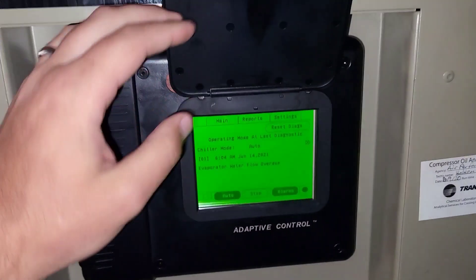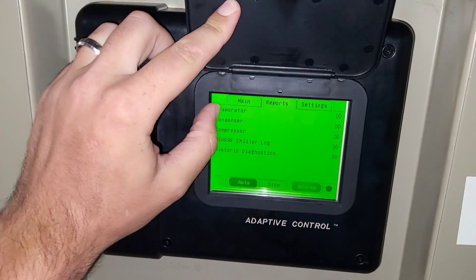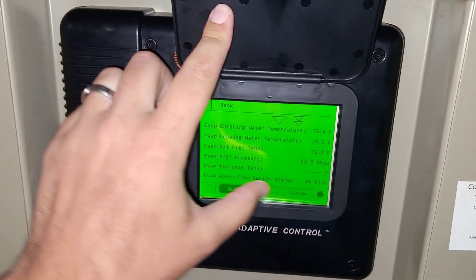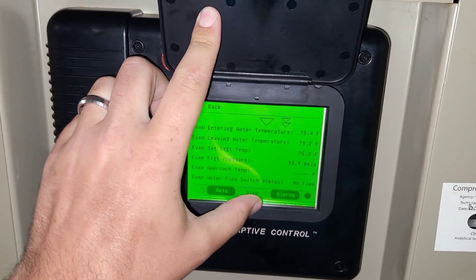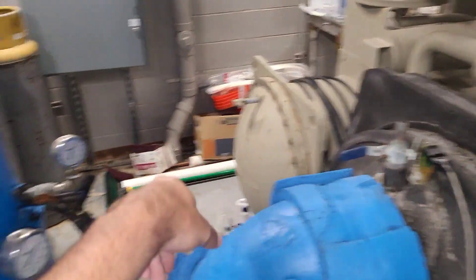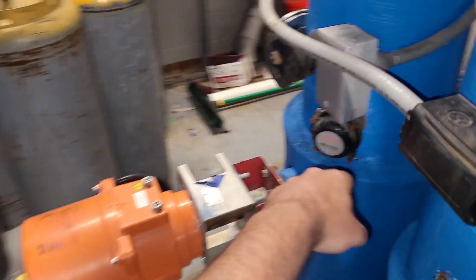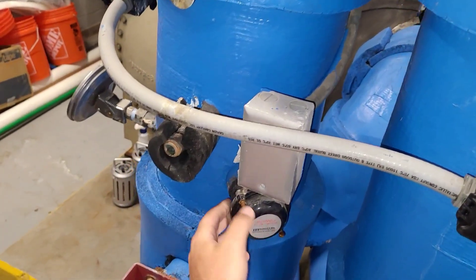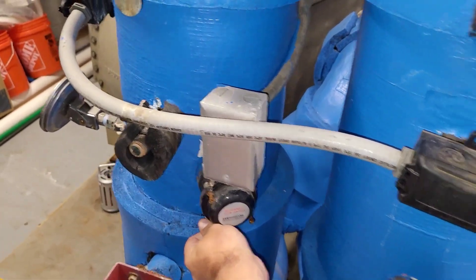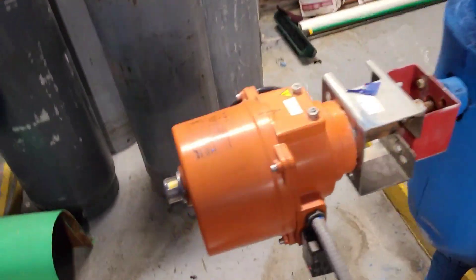So do we show flow right now? The operator shows no flow. All right, let's get the tool bag. We're going to open up the flow switch and see. This is just a paddle switch in here. It may have just gone bad. This is our overhaul we have going, by the way. The chiller's torn apart; we're waiting on the motor to come back.